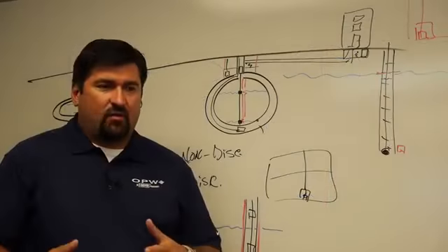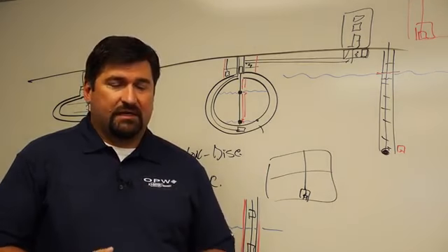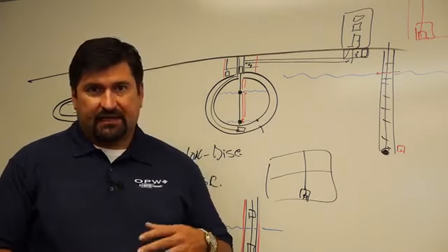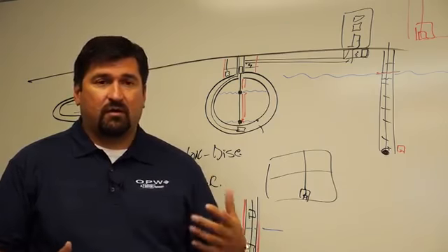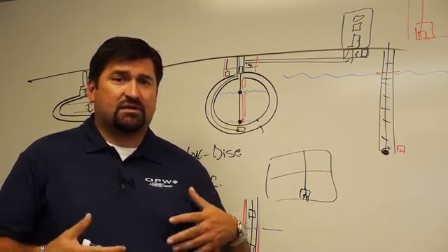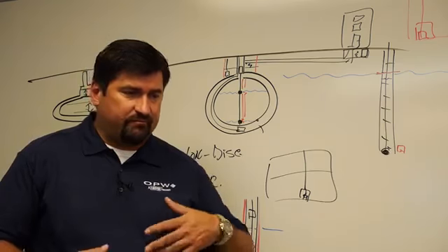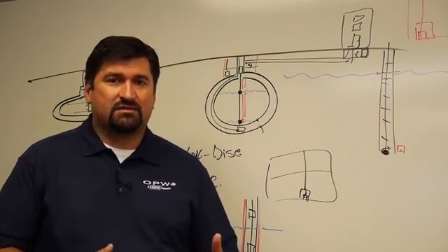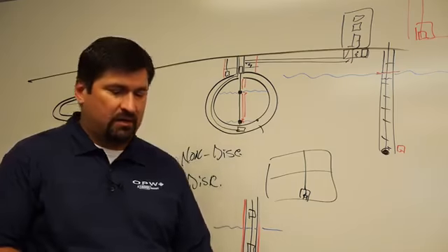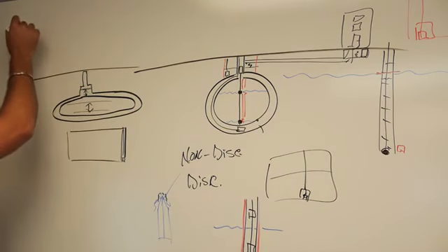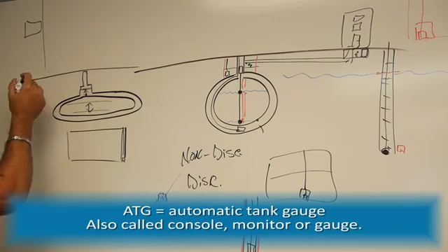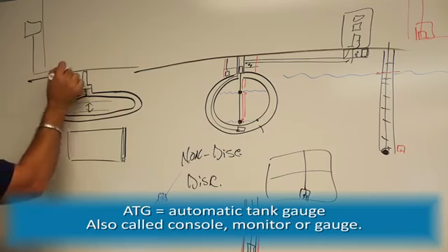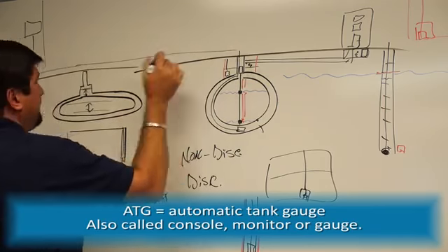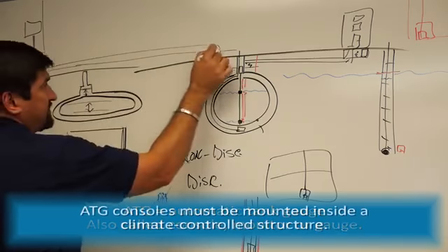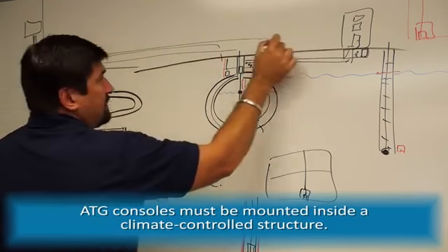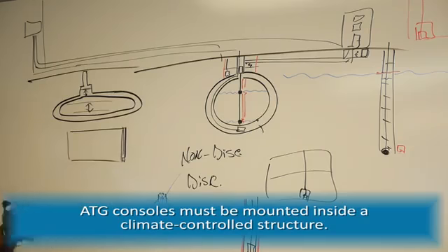So now that we talked about what's mounted out in the field, whether it be in the tank or in the annular space of the tank, in an STP sump or a monitoring well or a dispenser pan, they have to talk to something. Well, this is more affectionately known as an ATG console or a tank monitor. So if we mount the tank monitor inside the C-store, inside a building, we basically have to run wire to every one of these devices, and we're just monitoring this equipment through a wire going back to the building.